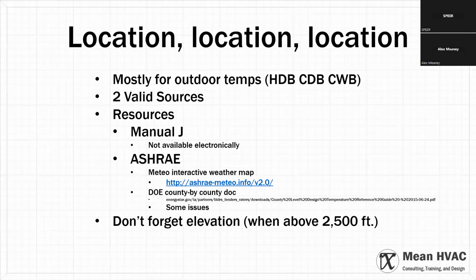But it also impacts equipment performance, both cooling and heating. And so once you get above 2,500 feet above sea level, you want your load adjusted because it starts to really make a difference around that height. And you can use some Manual S tables for derating the performance of heating and cooling systems. They get worse at altitude because they're not moving as much mass.